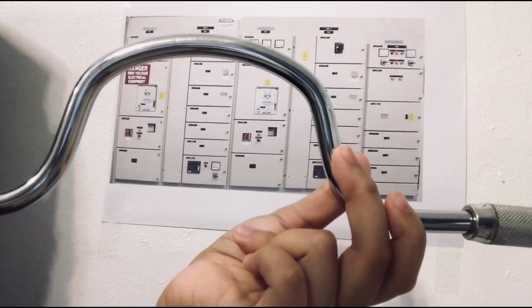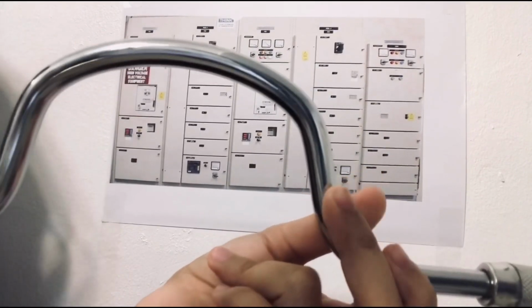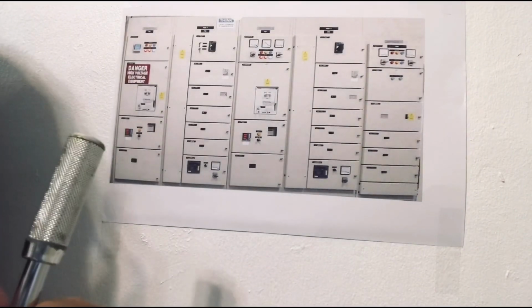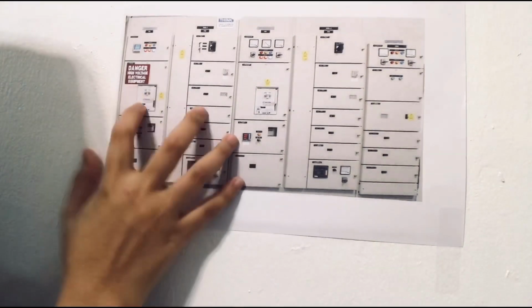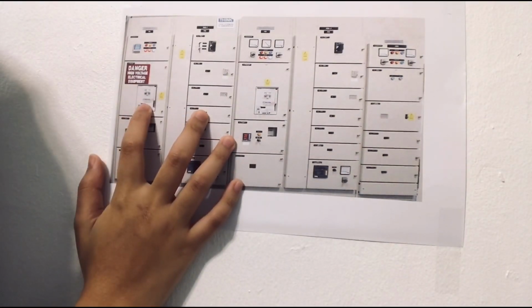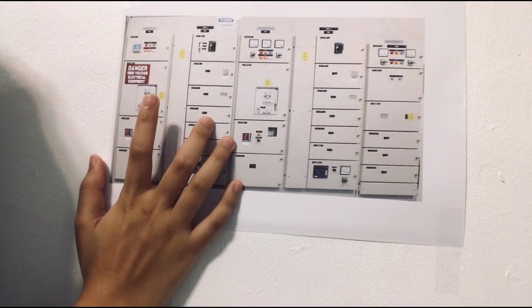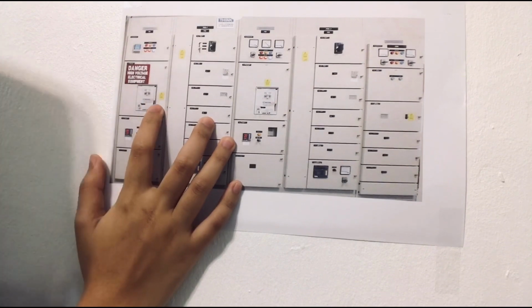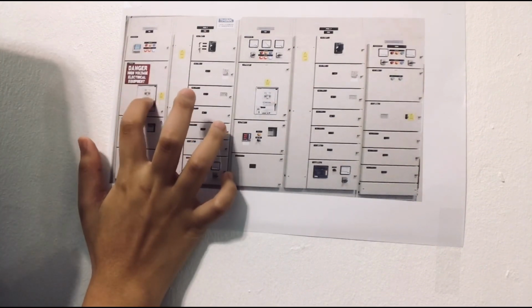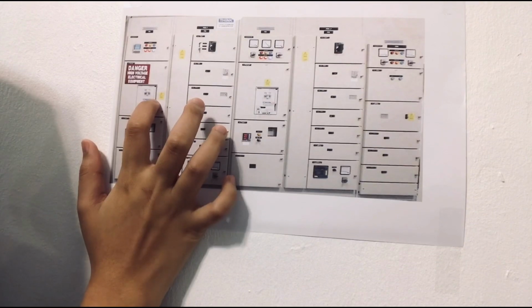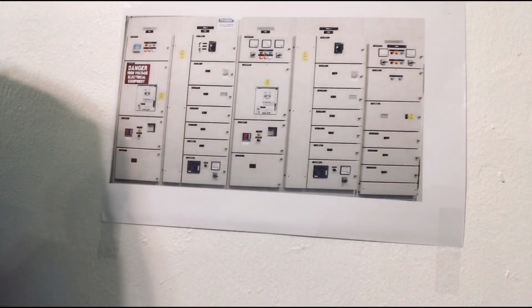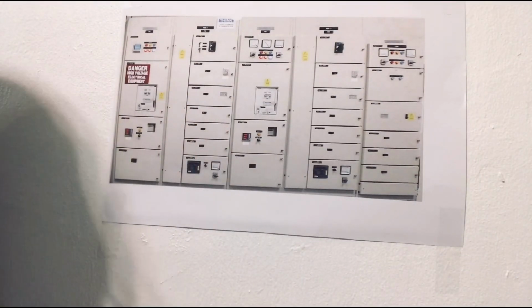This is the handling to connect ACB into the bus bar. To do that, we need to make sure ACB is in the off condition. We need to make sure ACB is in isolate condition, so we must change it to connect condition. At this panel, we can see either the ACB in the isolate condition or connect condition.